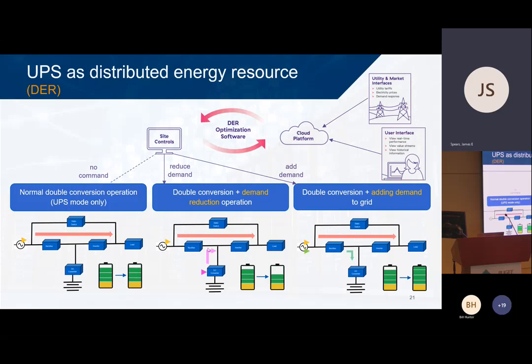And during that time, some of the energy to support the loads comes out of the battery, so less energy is coming into the UPS, and the battery does slowly discharge. We definitely do not want the battery to get down low enough to reach the yellow area at the bottom, because that is reserved for data center support. So we need to know exactly what the state of charge of the battery is while we're doing this. And with lead acid batteries, typically, we don't know that with a lot of accuracy. The lithium battery management systems do provide accurate and timely real-time state of charge information, and that's part of the reason we use lithium for this application.